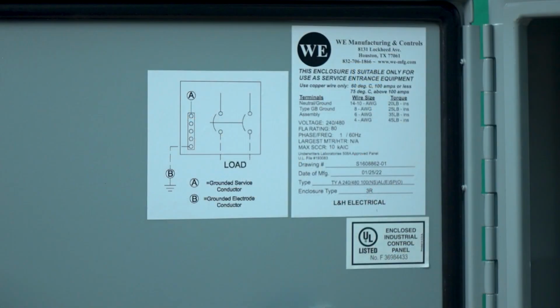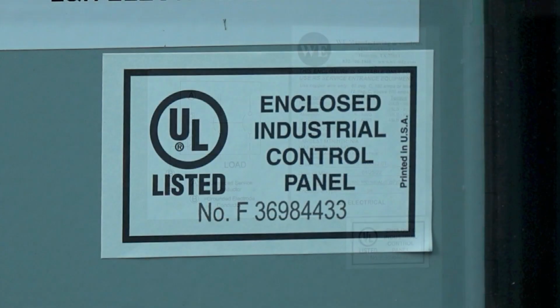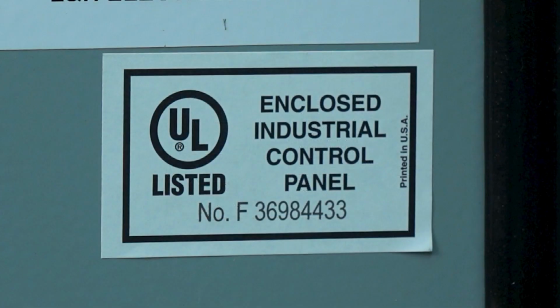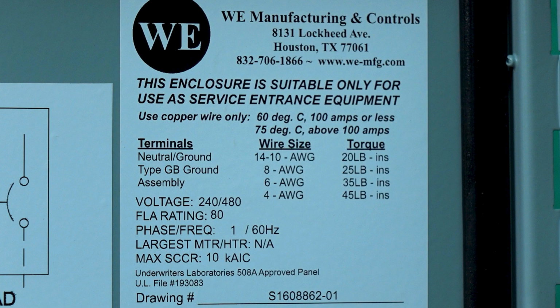On shop-built service assemblies and auxiliary equipment enclosures, the UL shop will place a permanent UL label inside the door of the enclosure with a unique serial number and the words Listed Enclosed Industrial Control Panel. On the same or a different label, the following information will also be shown: the name, location, and phone number of the shop, the UL file number of the 508A shop, the shop order or drawing number, the date of manufacture or assembly, and the line voltage.